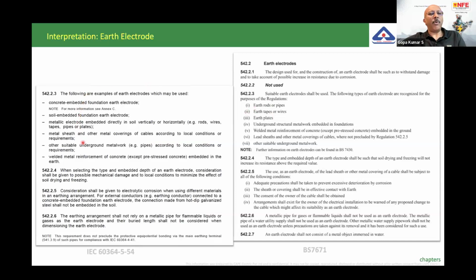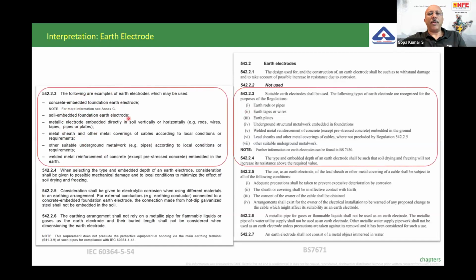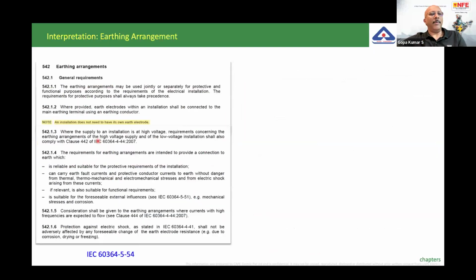The subject which is followed in the Indian standard is the same 542.2.3: concrete embedded foundation earth electrode, soil embedded foundation earth electrode. So from the IEC, basically these are the changes. This is an example of a change which is made in a local standard. For example, on the left side you are seeing the IEC, on the right side you are seeing the British standard. So the system on the left side is followed in India.